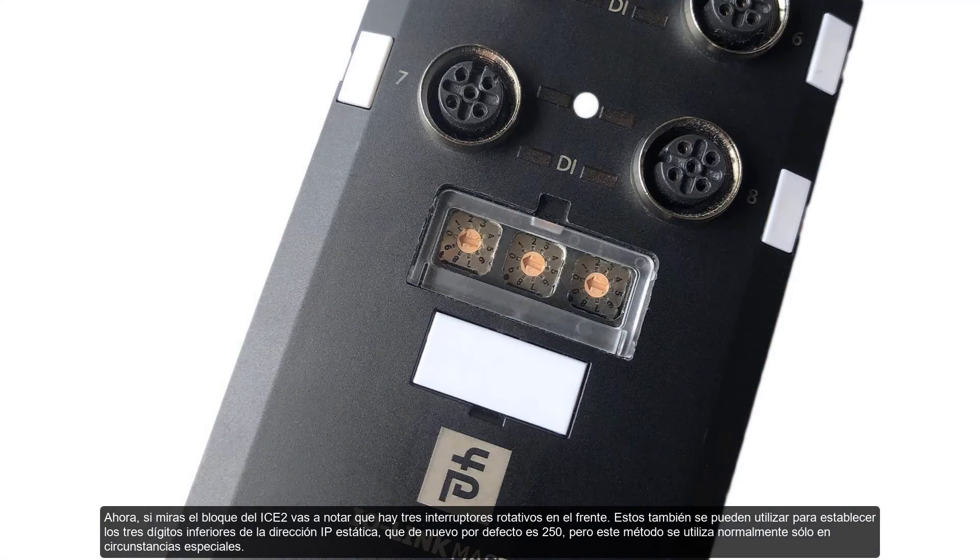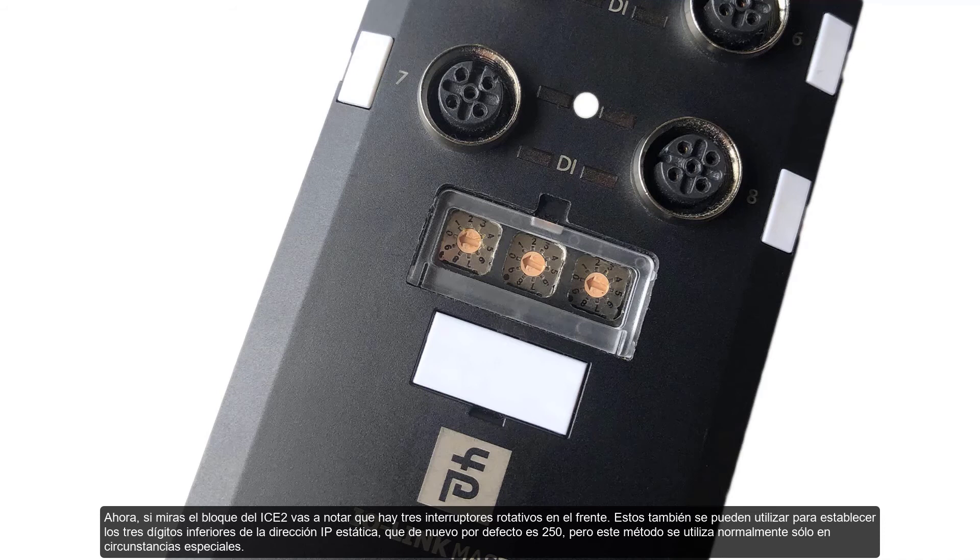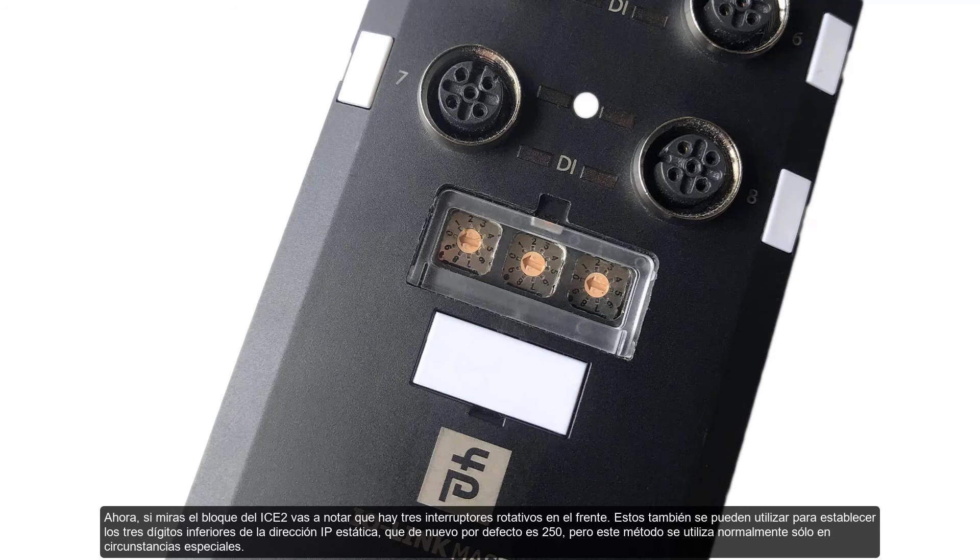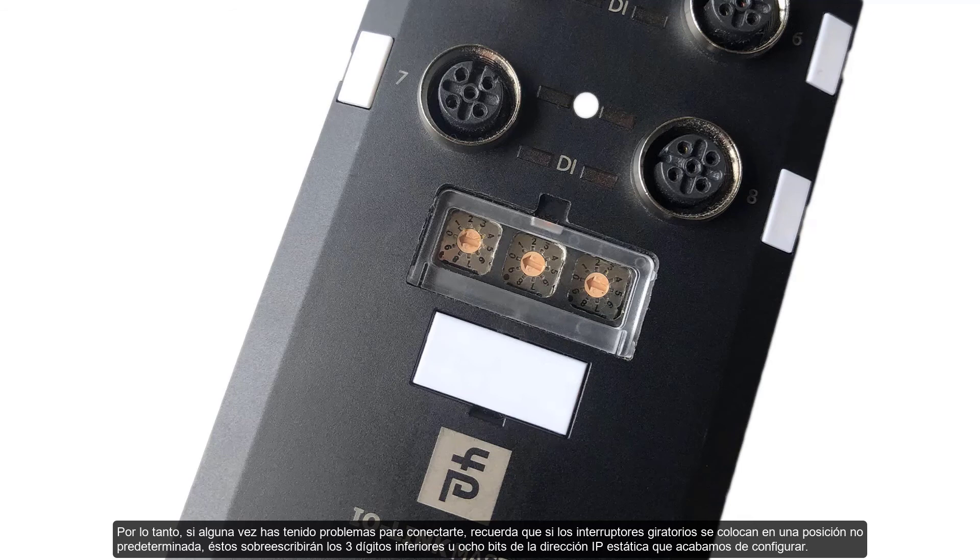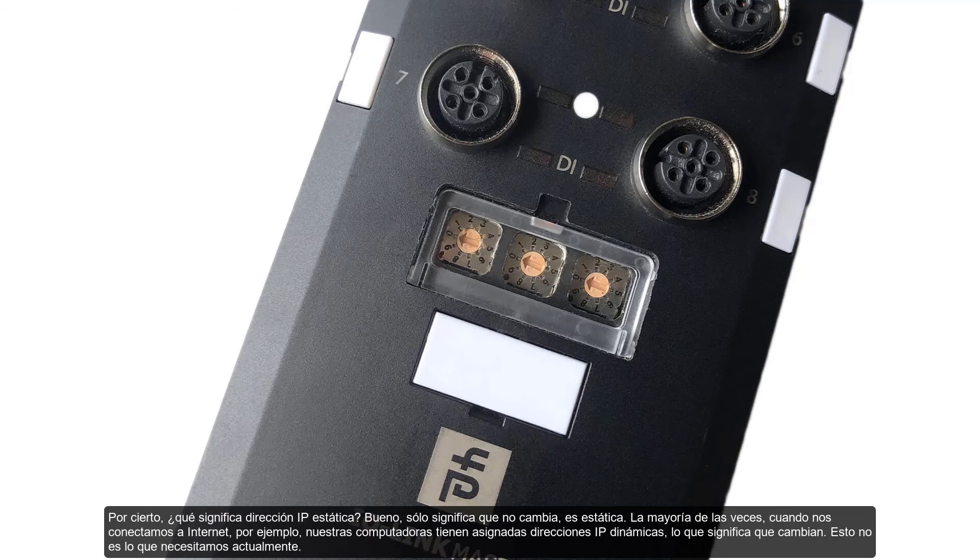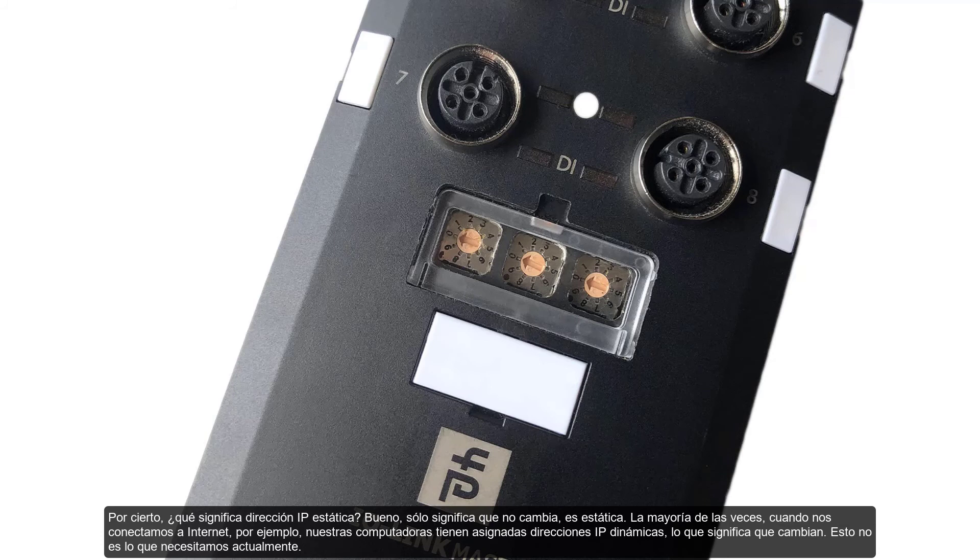Now, if you look at the ICE2 block, you're going to notice that there's three rotary switches on the front. These can also be used to set the lower three digits of the static IP address, which again by default is 250. But this method is usually only used in special circumstances. So if you've ever had trouble connecting, remember that if the rotary switches are set to a non-default position, the rotary switches override the lower three digits or eight bits of the static IP address, which we just configured. By the way, what does static IP address mean? Well, it just means that it doesn't change. It's static. Most of the time when we're connecting to the internet, for example, our computers are assigned dynamic IP addresses, which means that they change. This is not currently what we need.